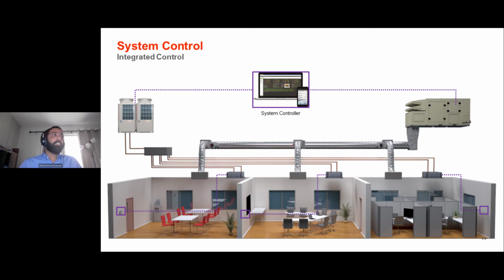This allows the end user access to the outdoor unit points, but more importantly, has proprietary analytics built into it that allow remote monitoring and diagnostics for every single piece of equipment on the system. It allows for 3 quarterly checks that are done remotely. A trained technician would run a report on every single piece of equipment and present those in an integrated and easily accessible form. And then one on-site check that would allow the trained technician to walk simply up to the units that have been highlighted as problematic and solve issues on them directly instead of going through the building and looking at every single piece of equipment. This allows for maintenance of VRF systems in a very non-intrusive fashion.